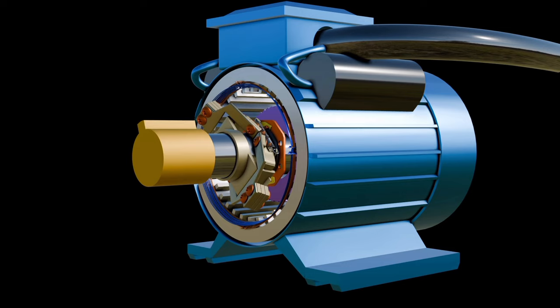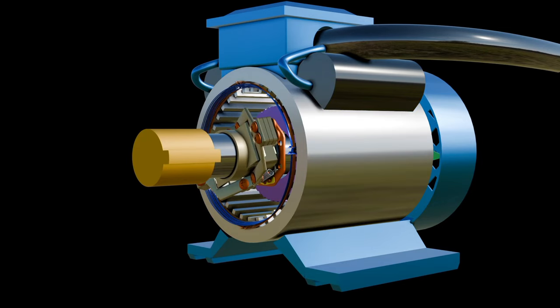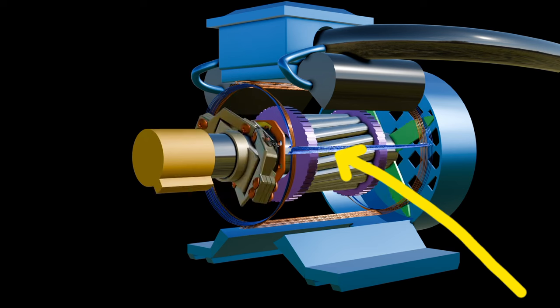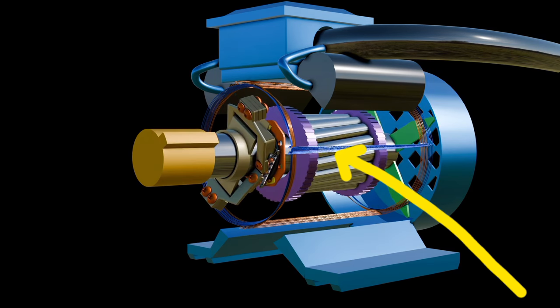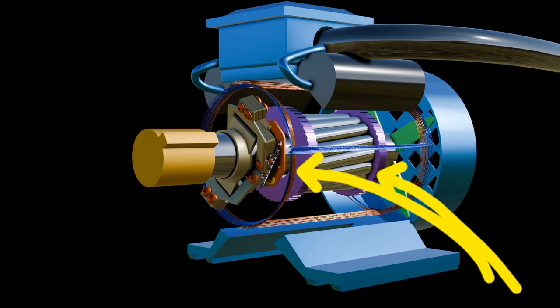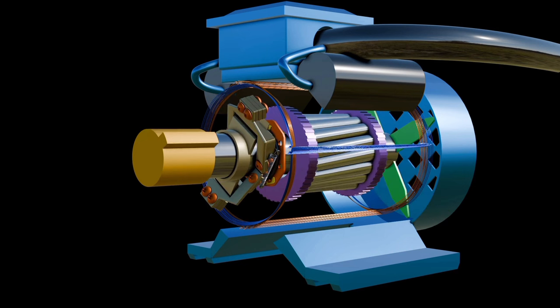The rotor in single-phase induction motors is the same as a rotor of squirrel cage induction motors. Instead of rotor winding, rotor bars are used and it is short-circuited at the end by endrings. Hence, it makes a complete path in the rotor circuit. The rotor bars are brazed to the endrings to increase the mechanical strength of the motor. The rotor slots are skewed at some angle to avoid magnetic coupling and also to make the rotor run smooth and quiet.